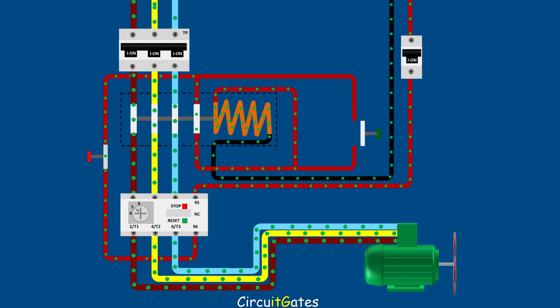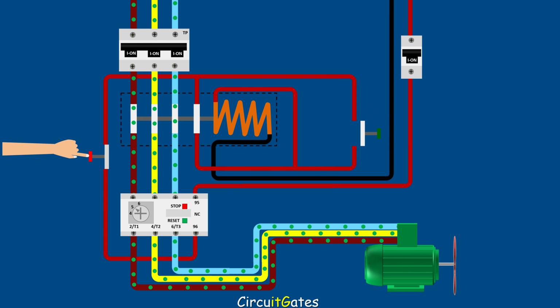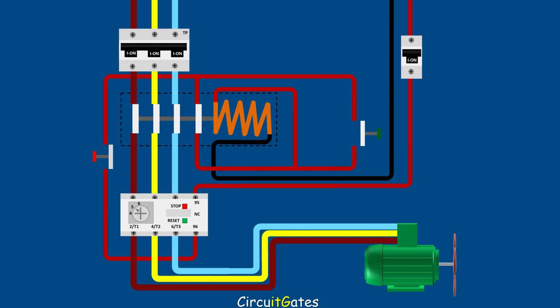To stop the electric motor, the stop button is pressed. This opens the circuit or cuts the supply of current to the contactor coil. When current through the contactor coil stops flowing, the contactor coil is de-energized and the contactor power contacts open. The opening of contactor power contacts cuts the supply of power to the electric motor and the electric motor stops running. Since the start button is a normal open contact, it prevents automatic starting of the electric motor in the event of stoppage because the circuit will be open.